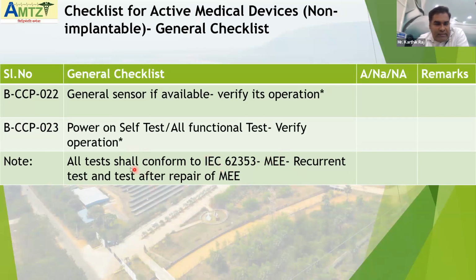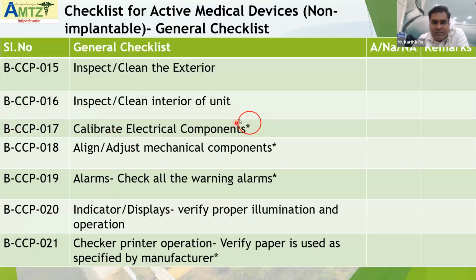This has to be confirmed, and in certain places you can see a star symbol. For example, point number 17, calibrate the electrical components. Whenever we say calibrate, it is not in our hands. We have to follow what the manufacturer says, and calibrate only those electrical components the manufacturer says to calibrate. If you do anything other than what the manufacturer says, the equipment's working on that part will be disturbed. So wherever the star symbol is shown, it means as per the manufacturer specification: calibrate electrical components as per the manufacturer specification. For certain points we have to refer to the manufacturer's service manual and follow what the manufacturer has defined.